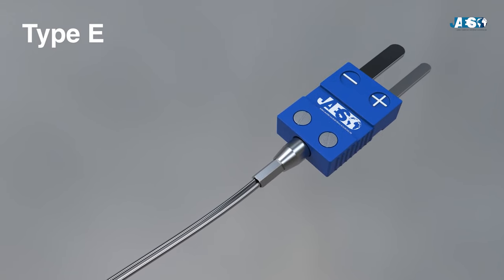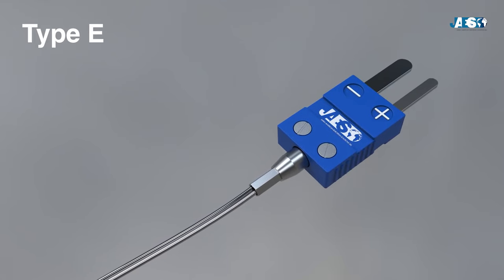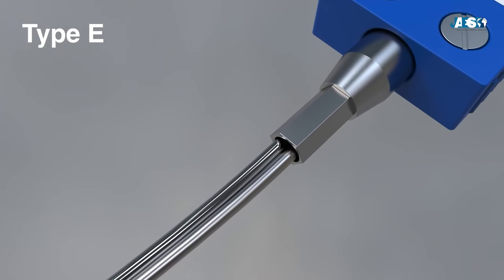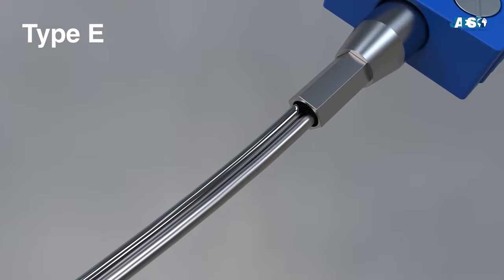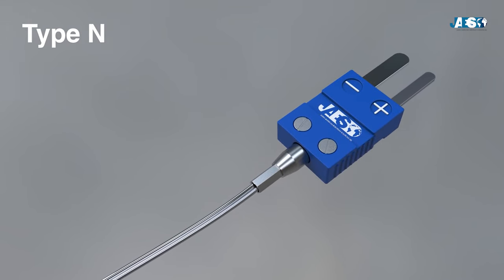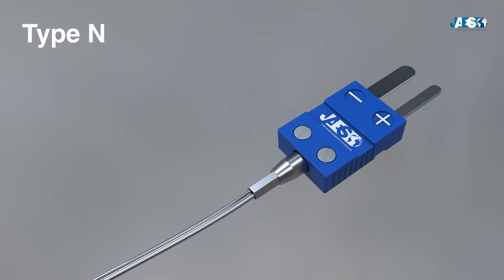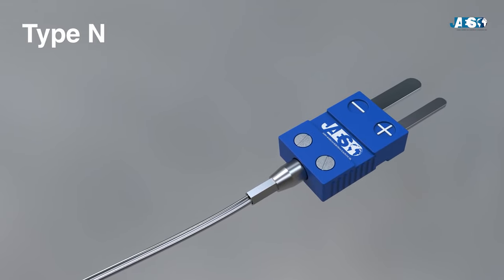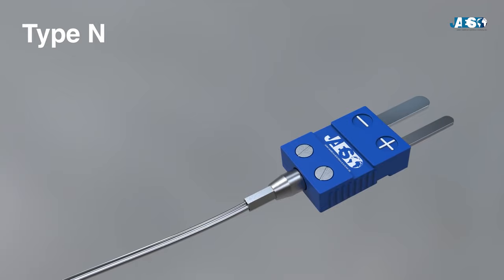Type E, composed of Chromel and Constantan, is suitable for perceiving low temperatures because it is very sensitive. Type N, composed of Nicrosil and Nisil, measures the interval between 650 degrees Celsius and 1,250 degrees Celsius.